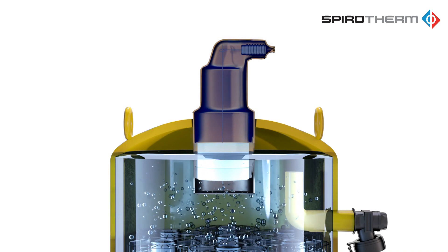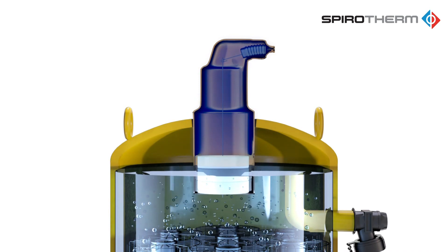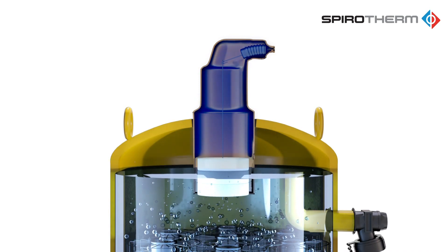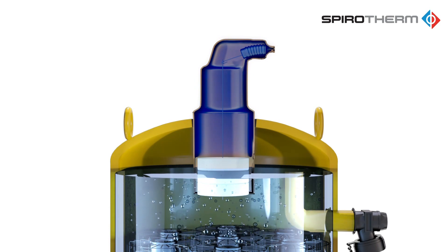The Spirovent is capable of eliminating 100% of the free and entrained air and up to 99.6% of the dissolved air, while continuously eliminating debris down to 5 micron.